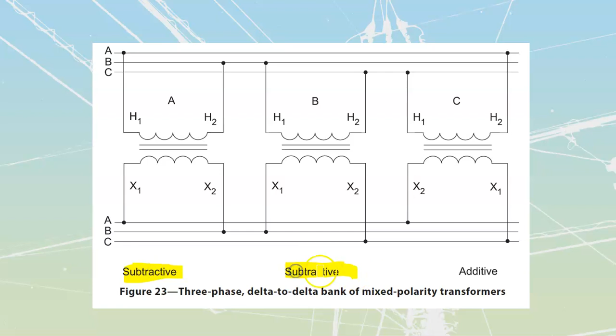Once again, just look at these low voltage connections - the primaries, the high voltage sides, are all correct. X1 of A goes to A, X1 of B phase goes to B, X1 of C phase goes to C, and then X2 of A goes to B, X2 of B goes to C, X2 of C goes back to A. Once again, the electricity doesn't really care - all that additive and subtractive means is that we've had a specific winding to that.